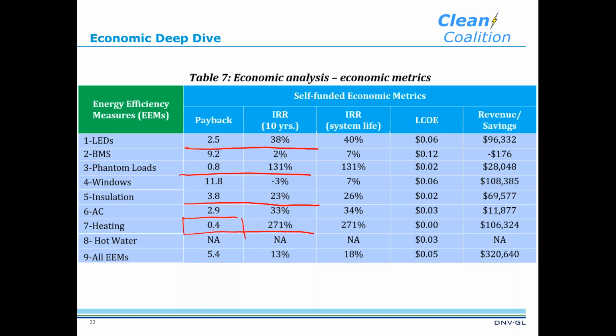The total savings -- what I really want to note here is that windows have a really long payback, typically 11.8 years, longer than the threshold most people could handle for windows alone. But once we bundle them all together, we can afford all the ECMs and have a bundled 5.5-year payback, which is pretty fast and really pays for itself. You end up with all new equipment, as long as you do it at the right time. The savings over the system life is $320,000, a substantial amount that can be spent on other parts of your building portfolio.